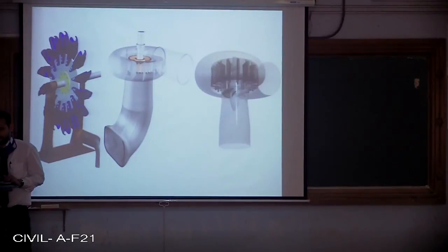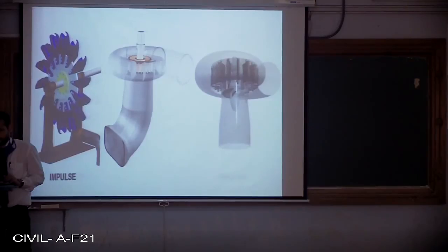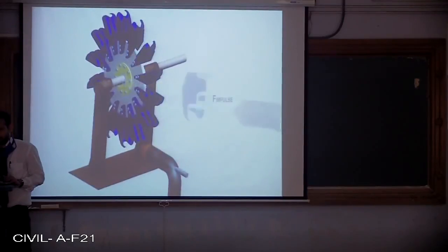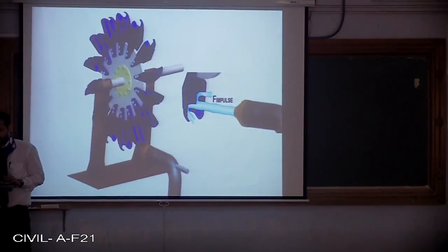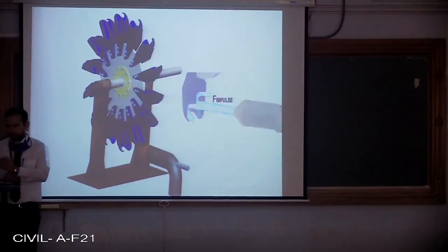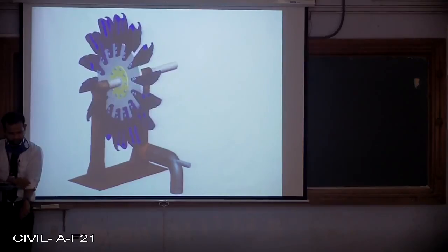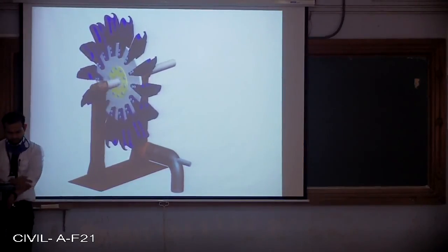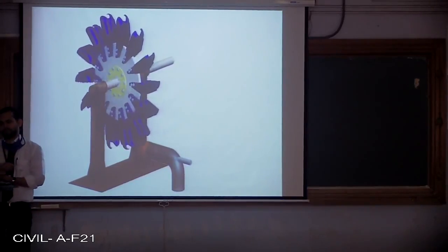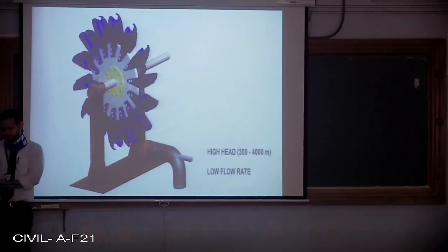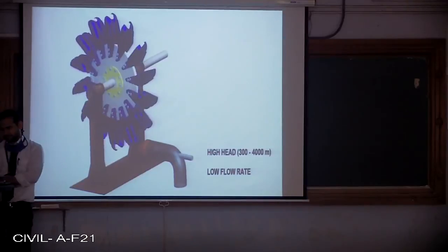When we move from Pelton to Kaplan, the force producing mechanism changes from impulse to reaction. In Pelton, pure impulse force of water jet is responsible for rotation of impeller. Water stored at high altitude can produce high impulse force due to its high velocity. So Pelton turbines are suitable for operation when water energy is available at high head and low flow rate.